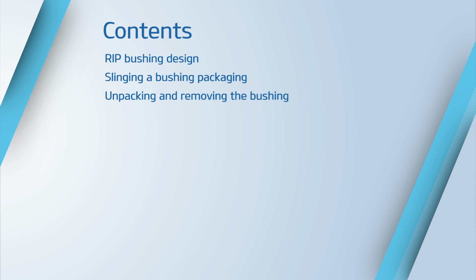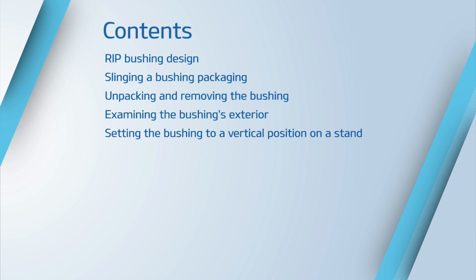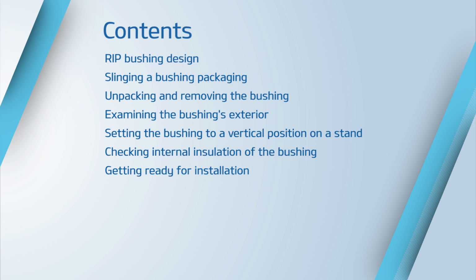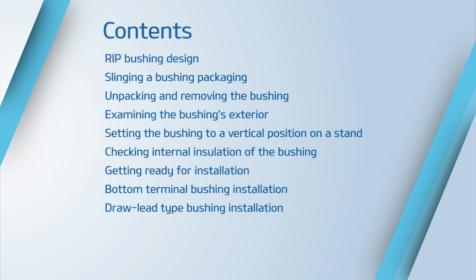Contents: RIP bushing design, slinging a bushing packaging, unpacking and removing the bushing, examining the bushing's exterior, setting the bushing to a vertical position on a stand, checking internal insulation of the bushing, getting ready for installation, bottom terminal bushing installation, draw-lead type bushing installation, conclusion.